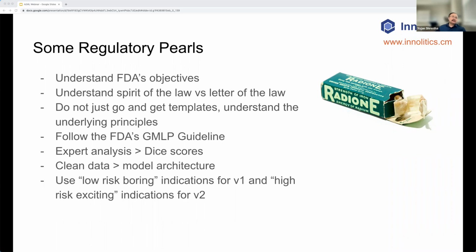Clean data is actually more important. Also, don't try to shoot for the moon on your first 510(k) submission. You should definitely consider phasing in different features. Maybe start out with the lowest risk features first, get 510(k) clearance for that, and then move on to more risky features for version 2. If you use this model, it will significantly reduce the time and cost of the FDA submission. One reason I've seen people be hesitant to release with half the features in version 1 and wait for a second 510(k) is that it seems very expensive and takes a long time. It can, but if you optimize the process, you can bring your features to the FDA in much smaller chunks, and that usually results in a better outcome for your business.